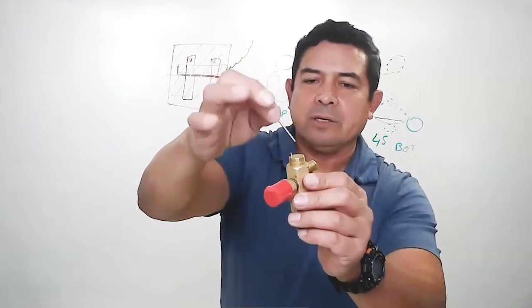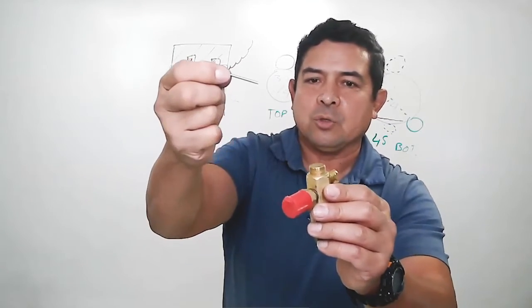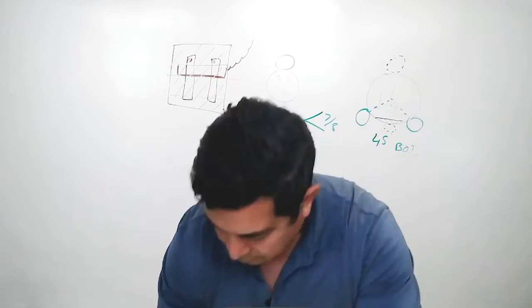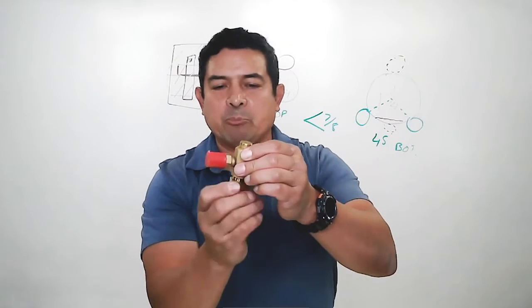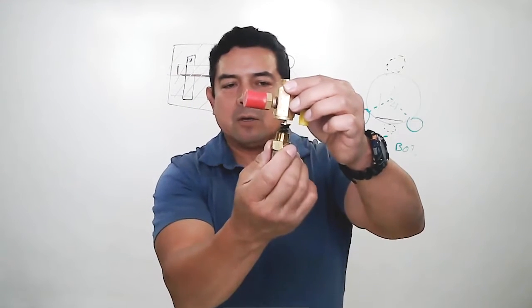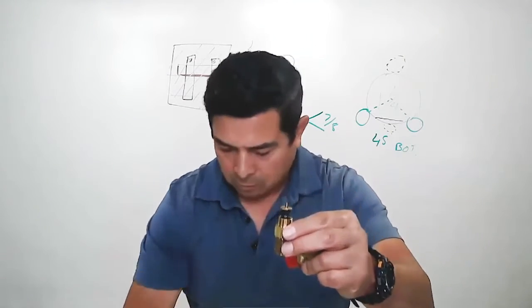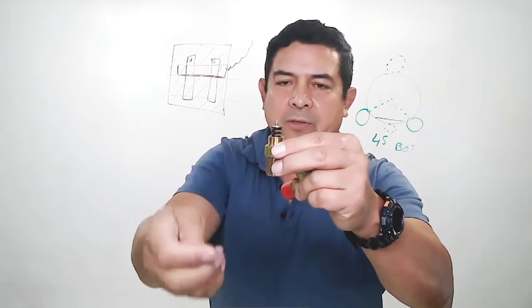So you have these two pins, one and two right there. These pins, what they're going to do is they're going to be pushed down by the diaphragm and those pins are going to be pushing down on the needle right here. You have two pins, one here and one here. They push down this. When they push down on this, it moves this down.